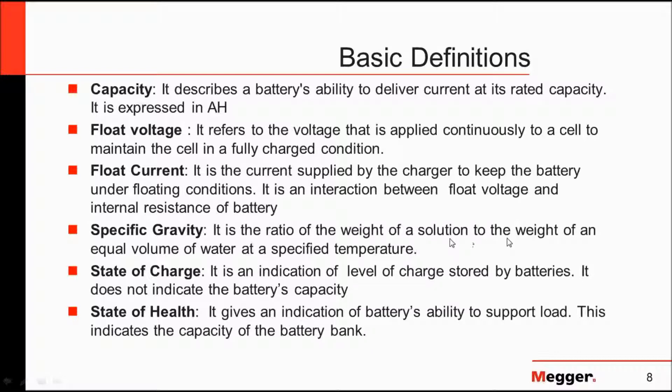Specific gravity is the ratio of weight of a solution to the weight of an equal volume of water at a specific temperature. State of charge is indicated by the level of charge stored in the battery; it does not indicate the battery's capacity and is measured through a voltage measurement of each individual cell. State of health is an indication of a battery's ability to support load, and can be obtained through two methods: automatic testing as well as a capacity discharge test.